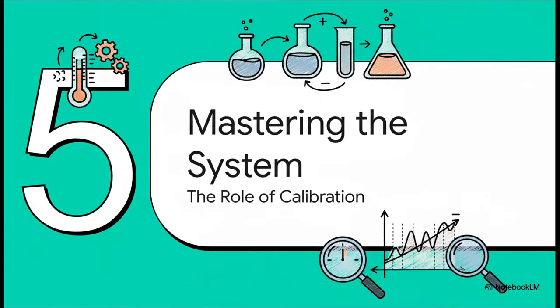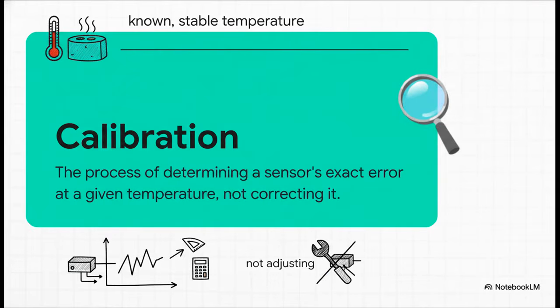All right, if you follow all those steps, you pick the right sensor, you use it correctly, you're going to get a very, very good measurement. But if you need absolute precision to master your system, then we have to talk about the final piece of the puzzle, and it's the one most people get wrong: calibration. Now, this is so important because there's a huge misconception out there. Most people think calibration means you're fixing or adjusting a sensor to make it read perfectly. That is not what it is. Calibration is simply the process of taking your sensor, putting it in a perfectly known temperature, and then precisely documenting its error. You're just figuring out exactly how far off it is.